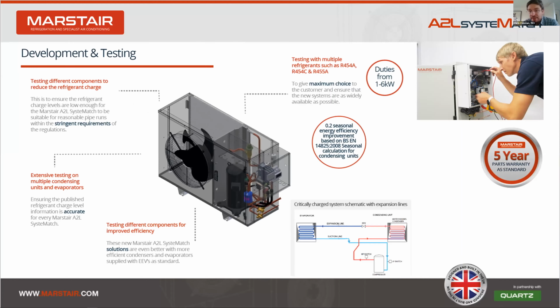Well, on developing and testing, we've been working on the project for the last 2 years and testing for the last 9 months. This includes work on reducing the refrigerant charging systems, for example, running on expansion lines. We've tested different system matches, so we know exactly what the refrigerant charge requirement is for each. And we've also improved the efficiency of the system by 3% compared to our original condensing units, which are already some of the most efficient on the market and are listed on the ETL website.